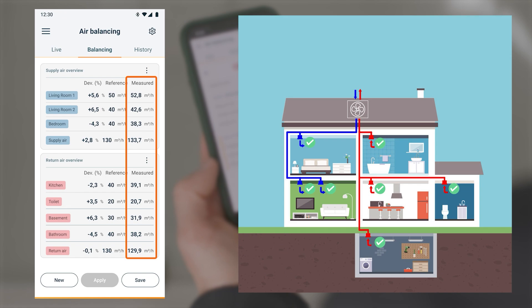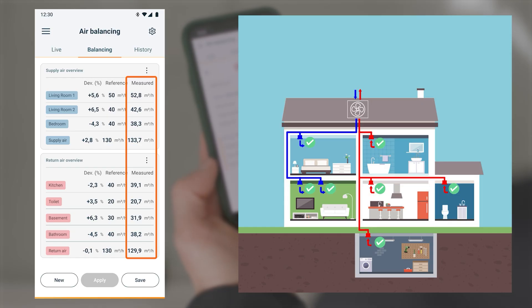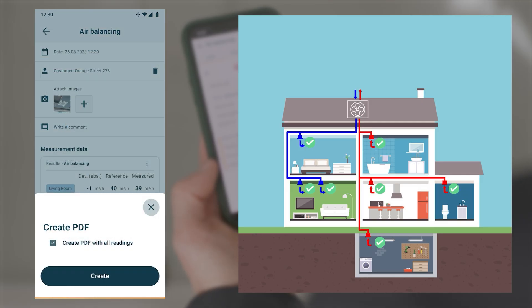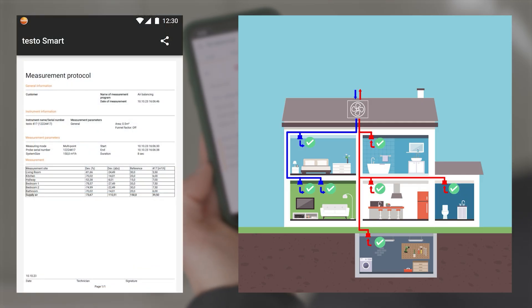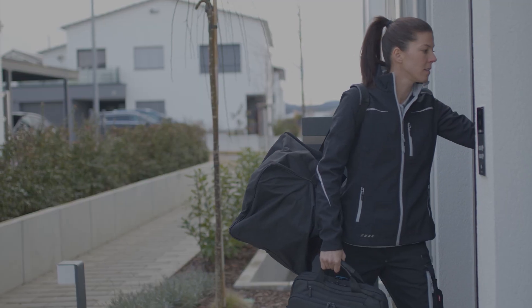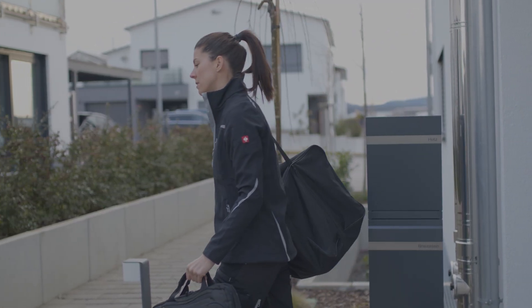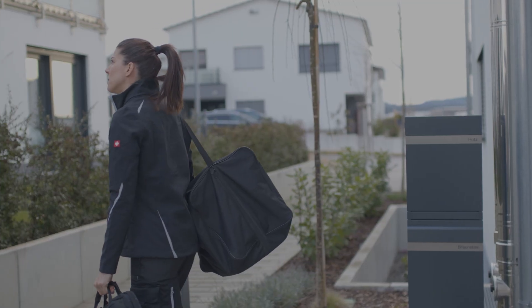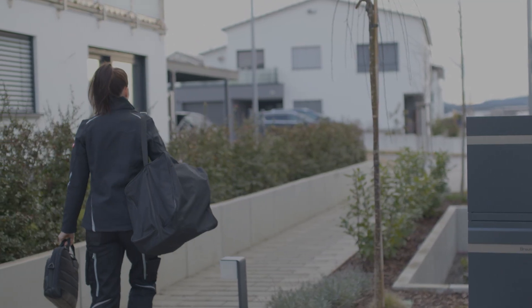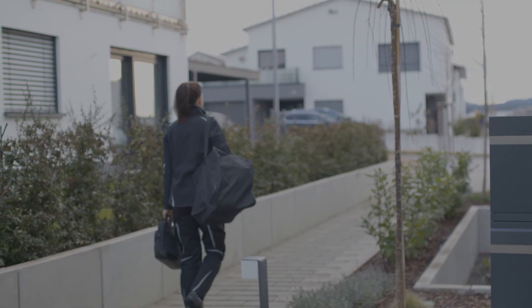The procedure is continued until all target volume flows of the outlets correspond to the reference. The number of measurement rounds can vary. The app recommendations help to reduce the number of measurement rounds. The final measured values can be clearly summarized and saved in a measurement report. This makes commissioning and balancing an air conditioning and ventilation system with the Testo 417 and the Smart Pro measurement program Air Balancing in the Testo Smart app quick, easy and efficient.